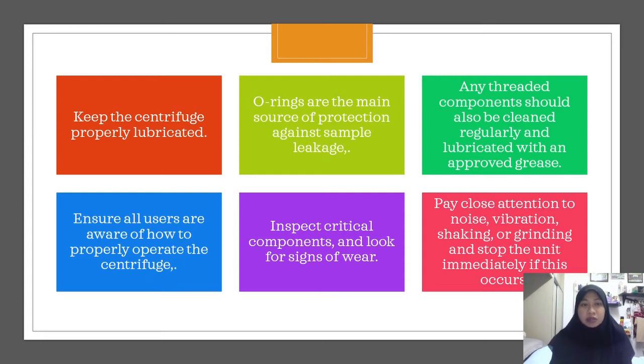Ensure all users are aware of how to properly operate the centrifuge. Inspect critical components and look for signs of wear, and also pay close attention to noise, vibration, shaking, or grinding, and stop the unit immediately if this occurs.